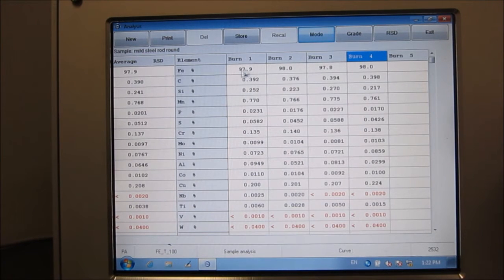Alright, so here you will see burn 1, you have a steel sample, it is actually a low alloy steel. You can see that it appears here that this was run by the subprogram FET100. Right? So here you see 4 burns have been done, and you will see the average value here. Alright, and if you want to take a look at the RSD, this can only be done when you have more than 3 burns on a certain sample.